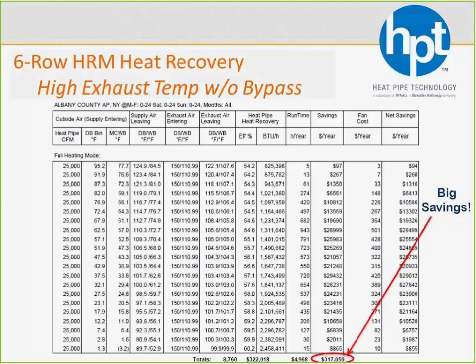So if you have any process type applications, the heat pipe makes perfect sense because not only are we going to give you year-round recovery and year-round savings, but we're going to do so at higher exhaust temperatures than other devices are going to allow you to do. And I did say that our max temperature is 200 degrees. If you have process heat that's above 200 degrees, that's fine. You can always dilute the air with some outside air to bring it down to 200 degrees to capture that heat. There are other systems out there, other heat pipes actually, that can handle higher temperatures, but they certainly cost more. So if it costs less to dilute the air in some way to use our heat pipe versus a more expensive type of heat pipe, it's probably in your best interest to do so, and we'll happily discuss that with you and see that it is.